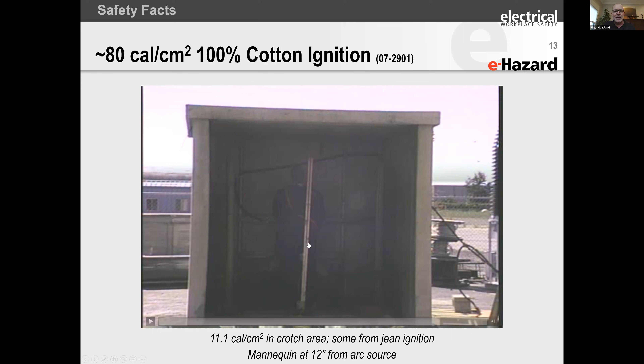So this is an arc that we did in a laboratory. We were replicating an accident, and we were looking at switchgear that could blow the energy out the bottom, and we were looking at a specific suit. If you look at this particular garment here, this garment's an 80 calorie long coat with leggings and non-flame resistant pants underneath. The trousers were non-flame resistant denim jeans. They caught on fire and burned the mannequin up. It's a wonderful time. But you can see that only 25% of the body was actually hit by that 80 calorie per centimeter squared electric arc. So arcs are very focused events.